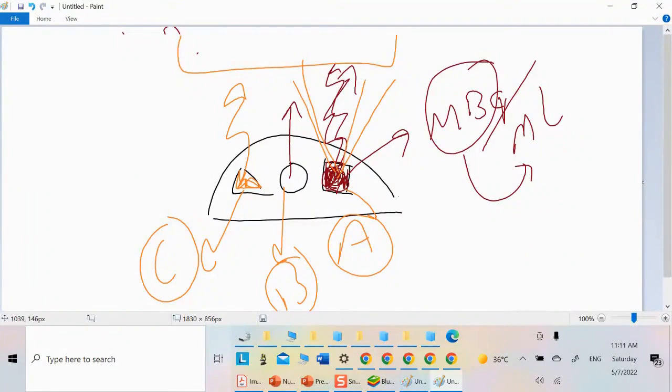This is going in a way that consequently the crystal cannot determine precisely where this photon is coming from. So when you come to do localization and determine the X and Y positioning with the XYZ circuit we talked about last time, the location is uncertain. That's why the topic of the collimator came up. So what did the collimator do for you? It said, I will draw like the grid we were talking about, and there are strips of lead, and there are holes. These holes only allow the photon coming perpendicularly to pass through. So that's what gets through and reaches the crystal.